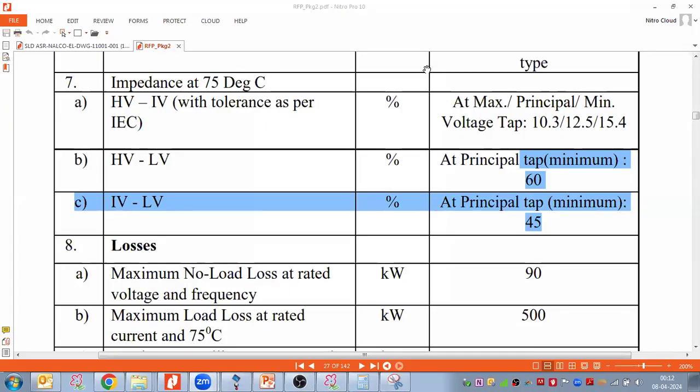For example, sir, if a 5 MVA transformer is there, and I have installed a 5 megawatt solar plant on this transformer, the active power is reduced now. So how can I manage the reactive power? Shall I install a 5 MVA SVG in parallel? Do not mix two different cases. Your case is solar. His case is static VAR generator. In your case, it is a different case.